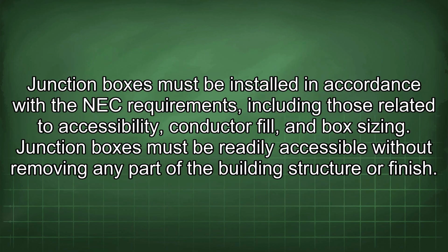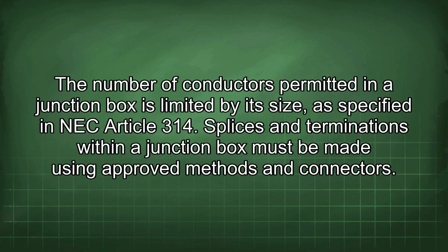Junction boxes must be installed in accordance with the NEC requirements, including those related to accessibility, conductor fill, and box sizing. Junction boxes must be readily accessible without removing any part of the building structure or finish. The number of conductors permitted in a junction box is limited by its size, as specified in NEC Article 314. Splices and terminations within a junction box must be made using approved methods and connectors.